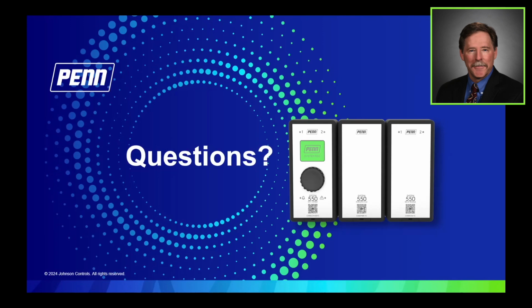The second way, it's hard to see in this photo or any other photos that we showed, but every one of our control modules has a USB-C port on the bottom left-hand side. And through a tethered connection to your computer, you can upload and download config files. And again, there's a program that you download. It's a shareware program, so you don't have to hit any buttons. If you're going to be in somewhat of an assembly process where you're going to upload the same config file to, let's say, 50 different control modules, you will simply upload the first one, unplug it. You'll get a message on the screen that the upload was complete. You'll unplug your USB cable and plug the next one in. Keep in mind that the controllers are getting power from the USB cable, so you don't even have to power the control modules.